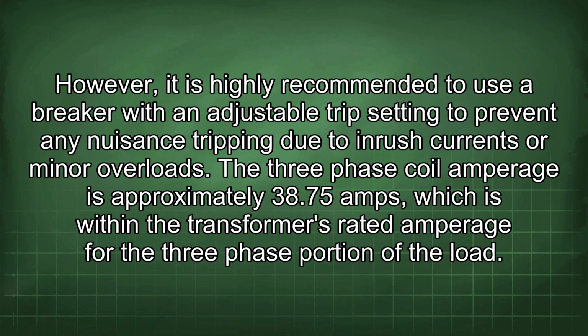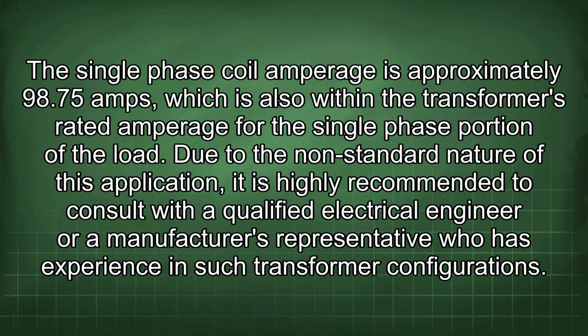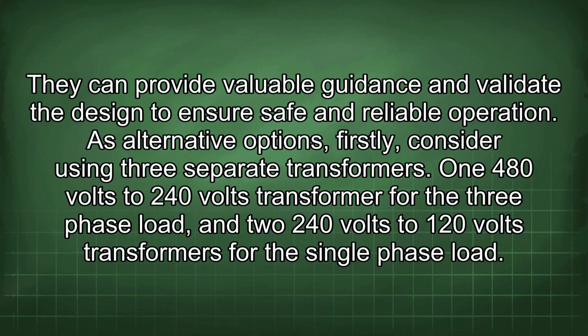The three-phase coil amperage is approximately 38.75 amps, which is within the transformer's rated amperage for the three-phase portion of the load. The single-phase coil amperage is approximately 98.75 amps, which is also within the transformer's rated amperage for the single-phase portion of the load. Due to the non-standard nature of this application, it is highly recommended to consult with a qualified electrical engineer or a manufacturer's representative who has experience in such transformer configurations. They can provide valuable guidance and validate the design to ensure safe and reliable operation.